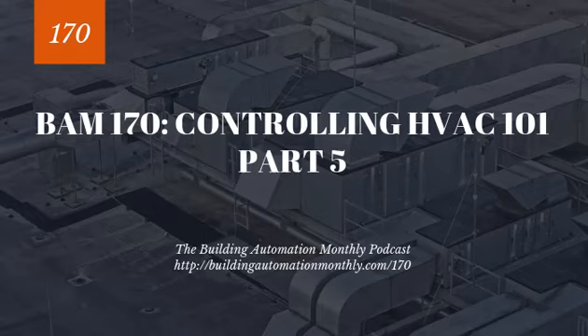instead of letting it flow through that primary loop. It's a confusing concept when you're listening to it from an audio perspective, but if you draw it out, in my opinion, when you get the timing right of the stage up and stage down and you get your loops tuned properly, this is actually one of the easier ones to control, decouplers. I actually like working with them versus using a mixing valve, because there's, in my opinion, less variables. Now, granted, it's a little more expensive because of all the flow sensors and things like that, but it is what it is.